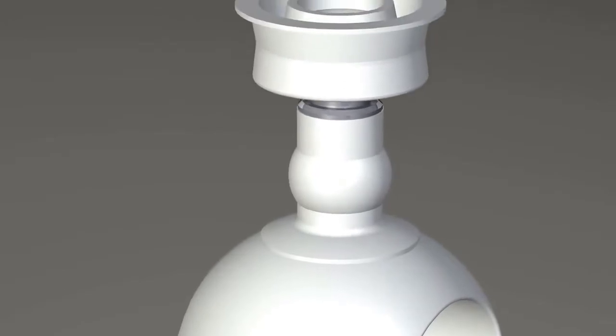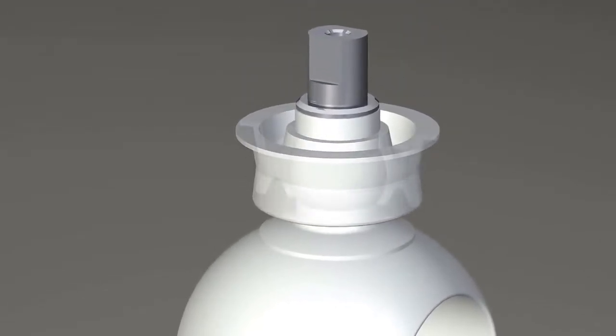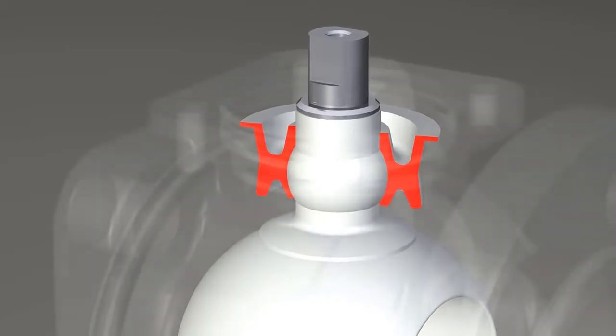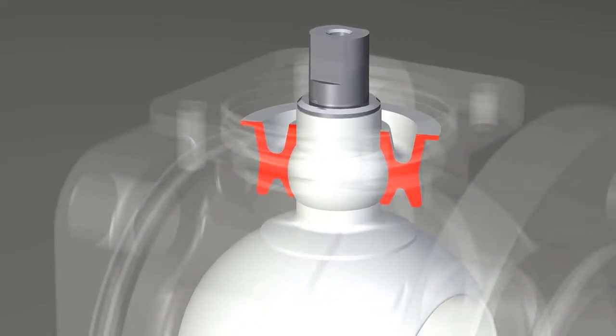The new patented Xomox SX seal with an X-shaped cross-section has been developed to create a tight seal between the media and the atmosphere. As the pressure is increased, it forces the seal against the valve body and the stem. The higher the pressure becomes, the more tightly the medium is sealed.